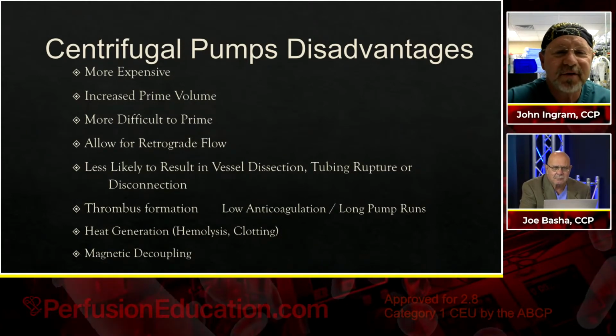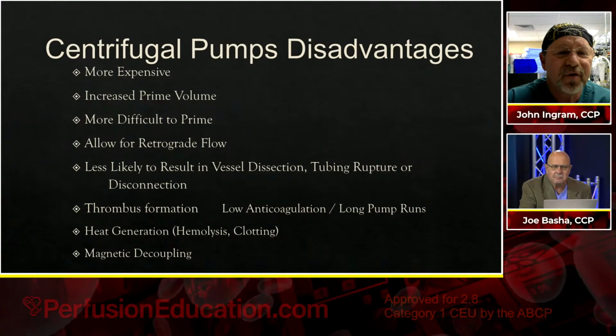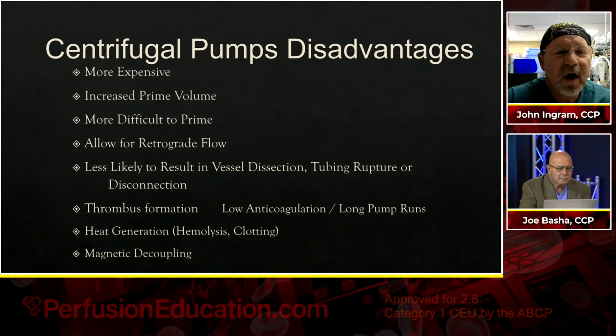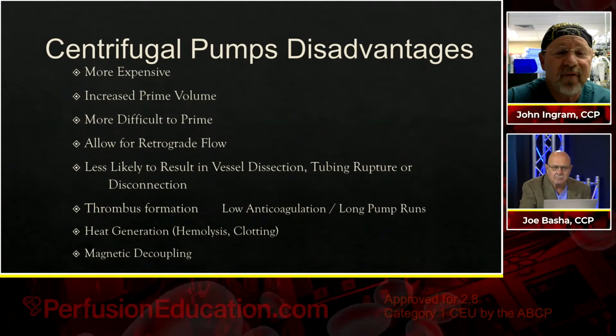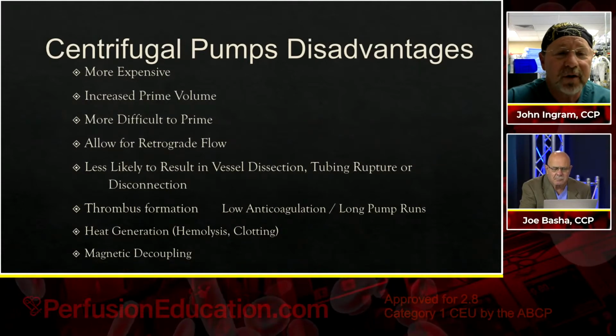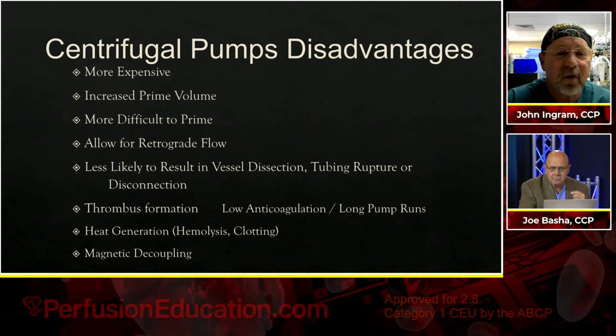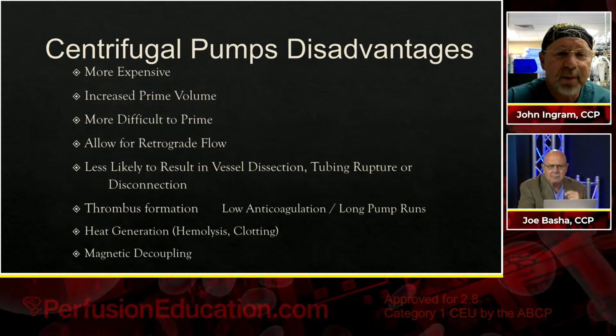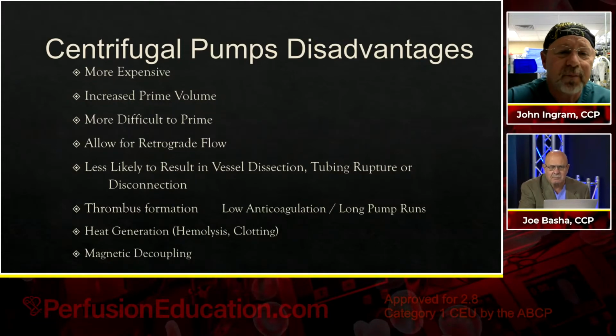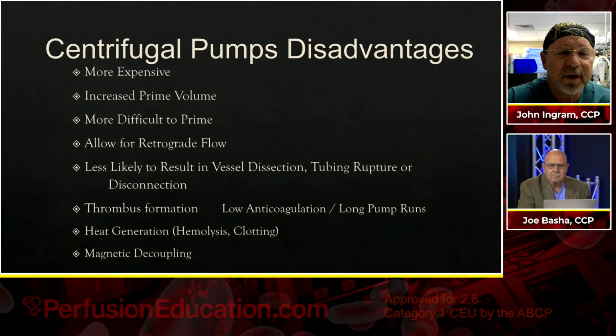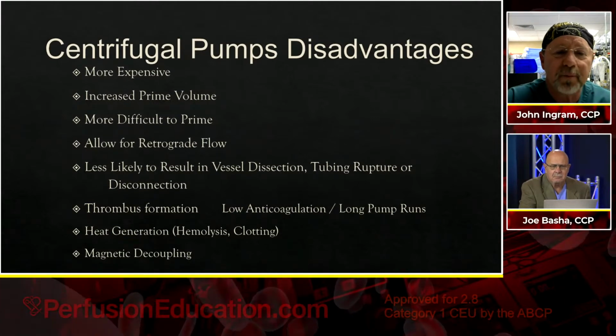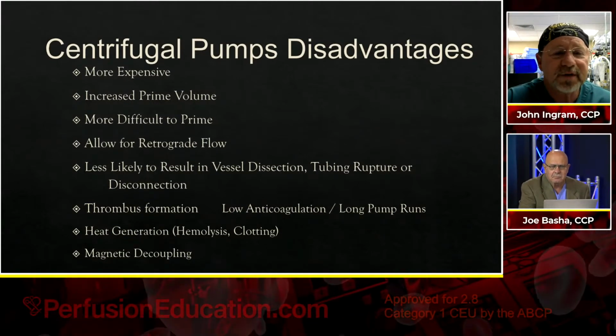So what are some of the disadvantages of centrifugal pumps? Well, they're more expensive. You're going to have larger prime volumes, quite a bit when you compare it to just a straight piece of tubing going through a roller pump. It's going to be more difficult to prime. You have to manipulate the pump to completely de-air it, whereas with a roller pump, it's going to push the air right through and prime itself.